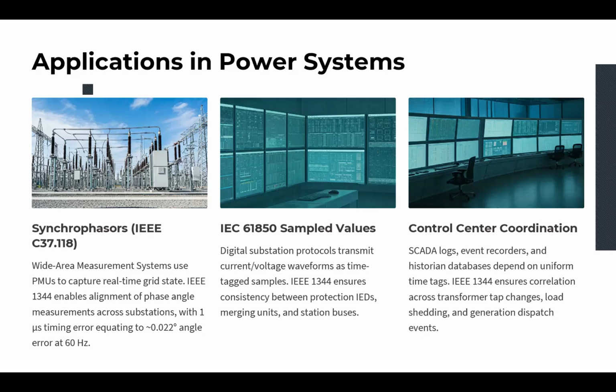Why that? Because 1 microsecond error translates to 0.022 degrees of phase error at 60 hertz. Now, IEEE 1344 basically enables this technology by, first of all, distributing sub-microsecond accurate time for all the PMUs, maintaining the logs and quality tags to trace the timestamp, and supporting fault detection in synchronization. When a PMU drifts and is out of sync, the angle measurement becomes useless and misleading. So it could lead to a false event detection or a missed alarm.